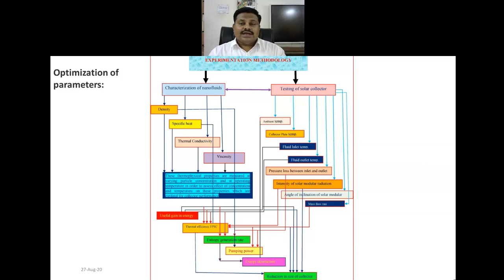As far as the testing of a solar collector is concerned, ambient temperature, collector plate temperature, fluid inlet temperature, fluid outlet temperature, pressure loss between inlet and outlet, intensity of solar radiation, angle of inclination of solar module, mass flow rate all need to be optimized to have good performance. The output parameters are whether there is useful energy gain, whether the thermal efficiency of the flat plate solar collector is good, whether the entropy generation rate is good, pumping power is proper, exergy destruction, and reduction in size of the collector. These parameters become very vital while combining nanofluids and solar collectors together.